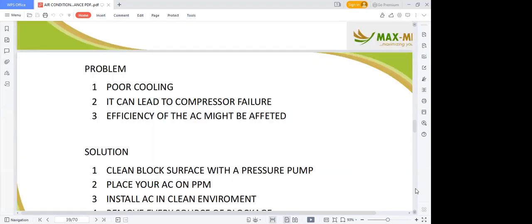Poor cooling can lead to compressor failure, because if the compressor is not getting the refrigerant back to the required temperature, then the compressor will shut down. So it has a direct impact on your outdoor unit. The efficiency of the AC might be affected because what's supposed to blow out, dirt is blocking it. It's not allowing it to go out. So people will be complaining, why is this place hot and the AC is working? Only for you to open and discover there's ice forming on top of your evaporator coil. So you might need to do your maintenance well.